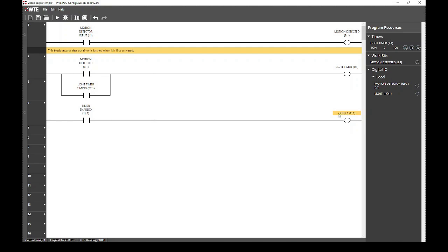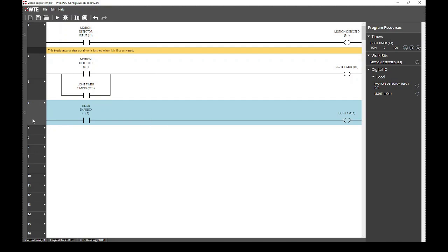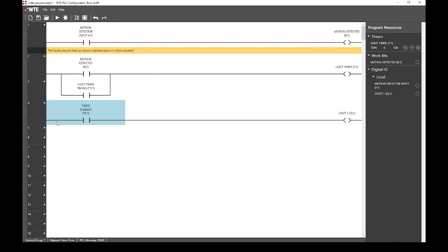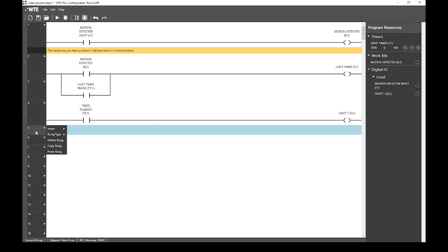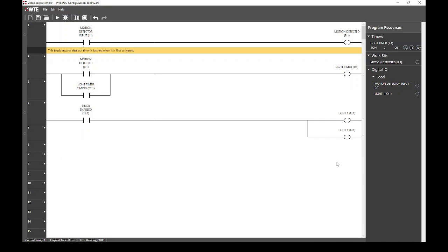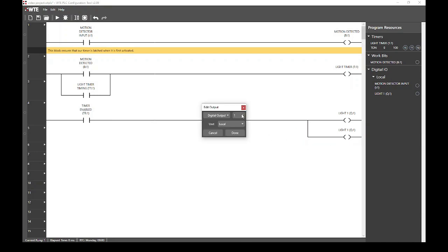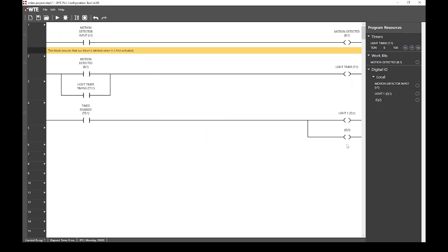Next, we also want to be able to control light 2, which is attached to digital output 2. We can do this quickly by selecting this rung and selecting copy rung. Next, we go to rung 5 and select paste rung. As you can see, this has branched the output for rung 4. Next, we select this output and we change that to digital output 2. Click done, give it a descriptive name, light 2. And now our timer is controlling our lights.